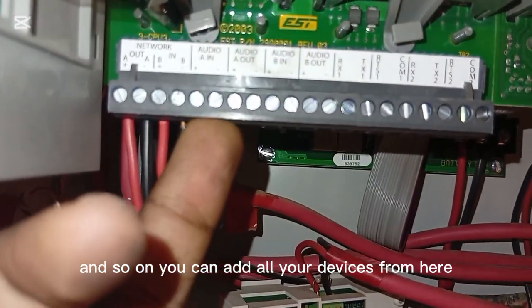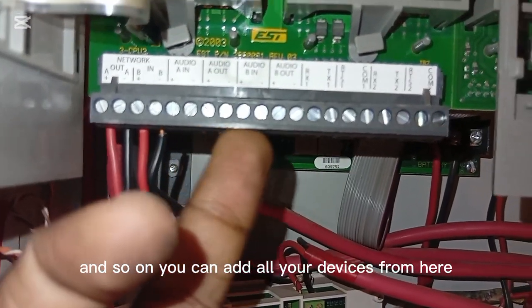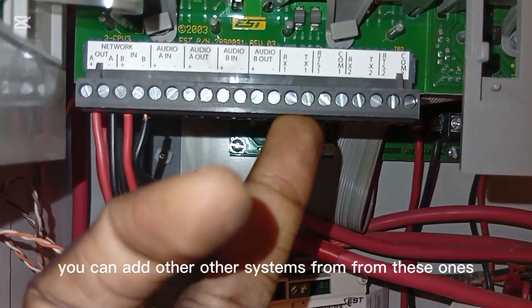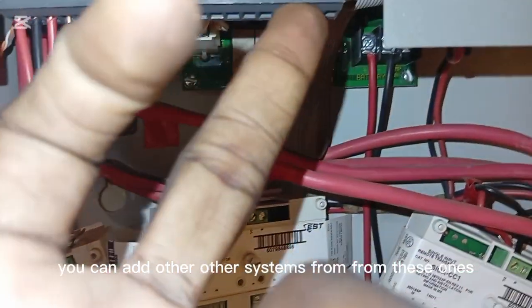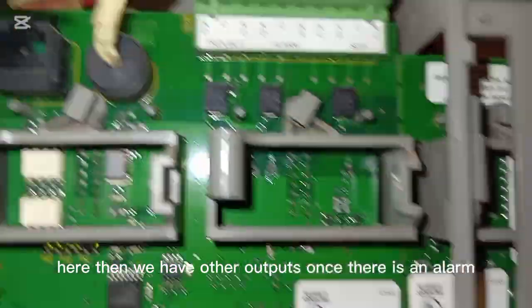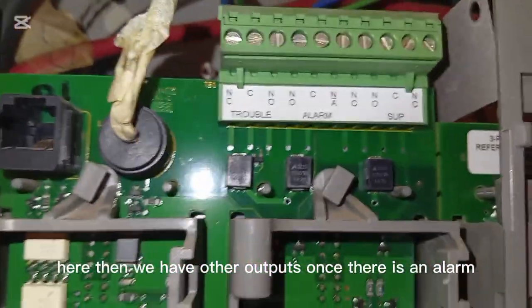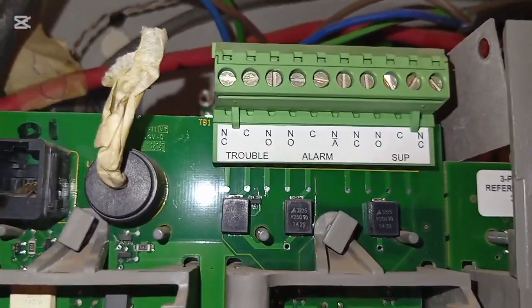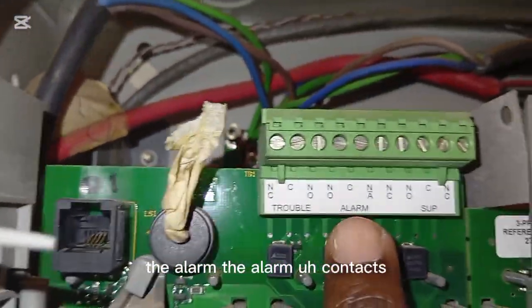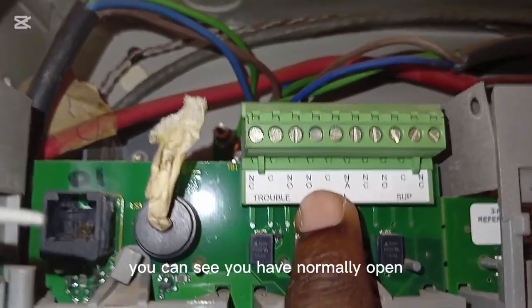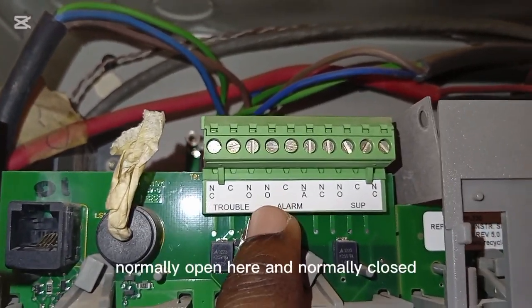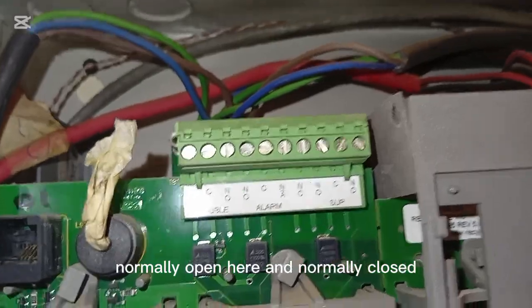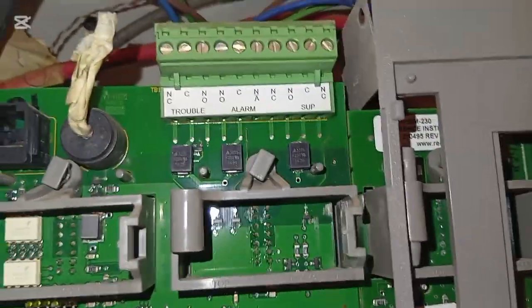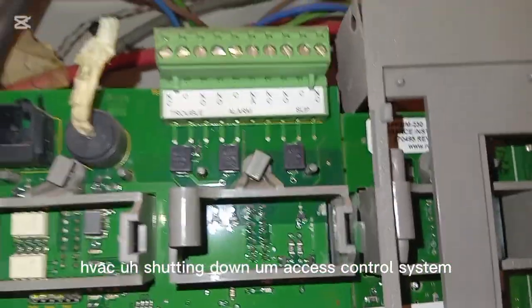And so on, you can add all your devices from here. You can add other systems from these ones here. Then we have other outputs. Once there is an alarm, the alarm contact, you can see you have normally open here and normally closed. So you can control other circuits like lift, HVAC, shutting down the access control system.